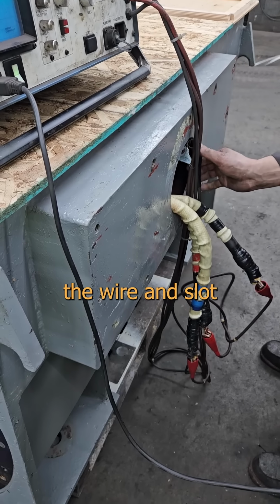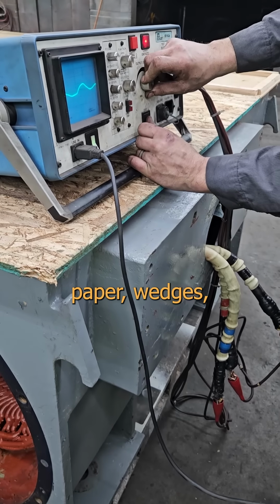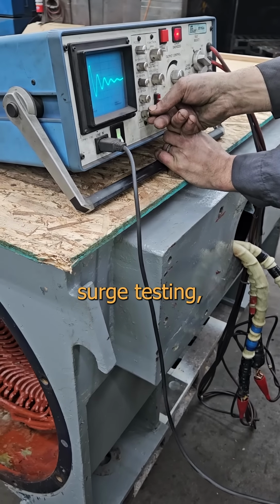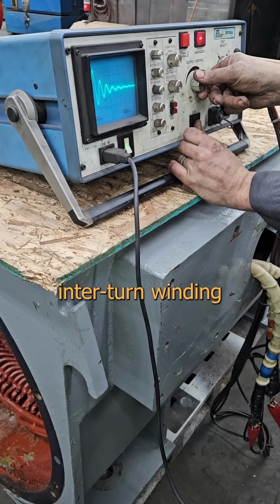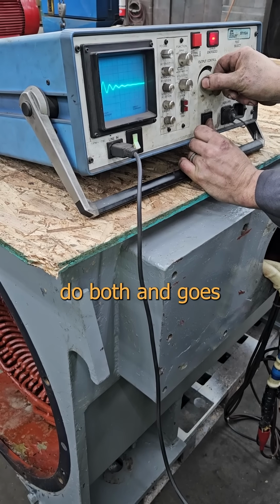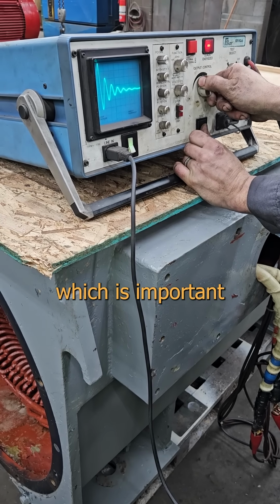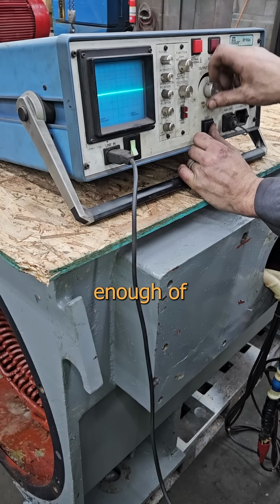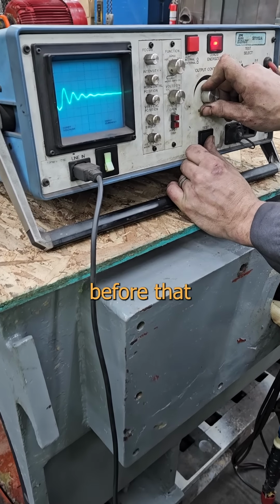High pot tests the wire and slot liner insulation, phase paper, wedges, and varnish. There's also surge testing, which finds faults in interturn winding and phase-to-phase insulation. This one will do both and goes all the way up to 12 kilovolts, which is important to remember, because if you do enough of these tests, it's only a matter of time before that thing bites you.